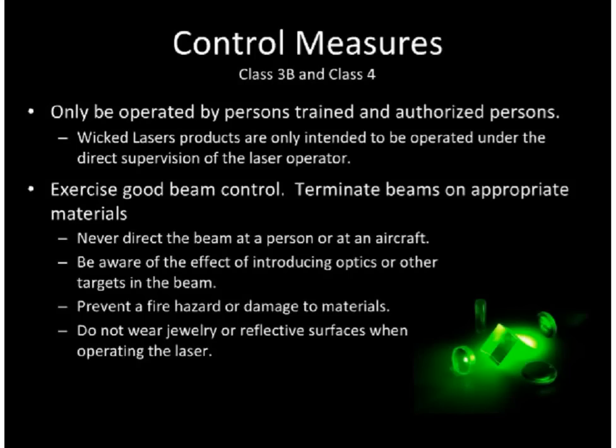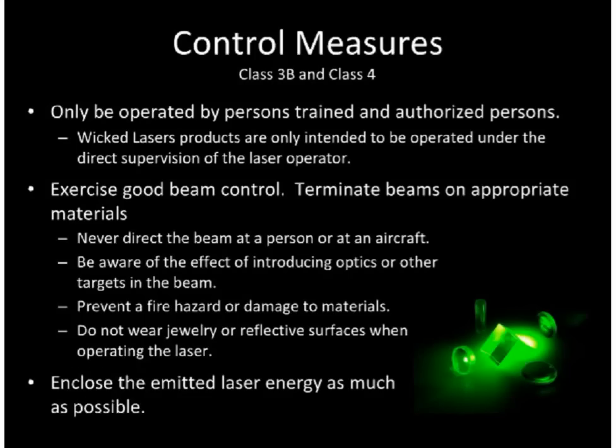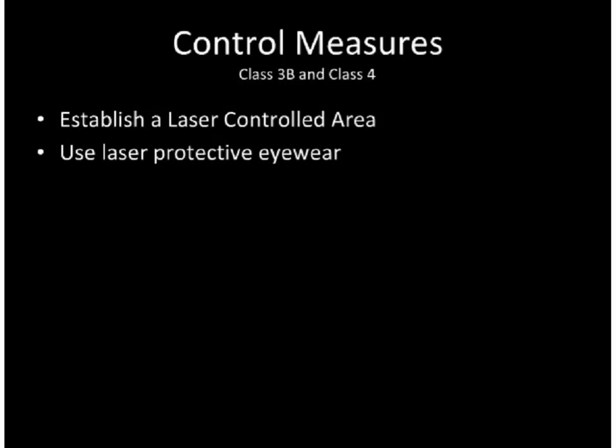Do not wear jewelry or reflective surfaces when operating the laser. Enclose the emitted laser energy as much as possible. Enclosures need to be made of materials that will not transmit levels of laser light above the maximum permissible exposure or be subject to damage from the anticipated laser exposure. Establish a laser control area that should contain the nominal hazard zone. Anyone occupying this area while the laser is operated must be protected from all laser hazards, and all unnecessary personnel should be located outside the controlled area when the laser is operational.